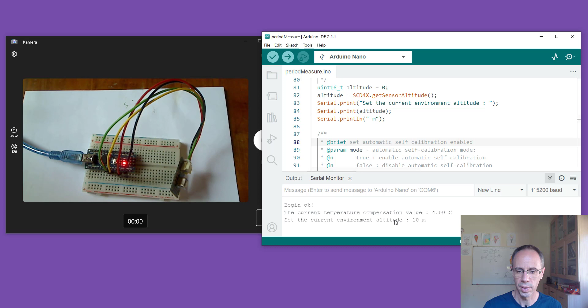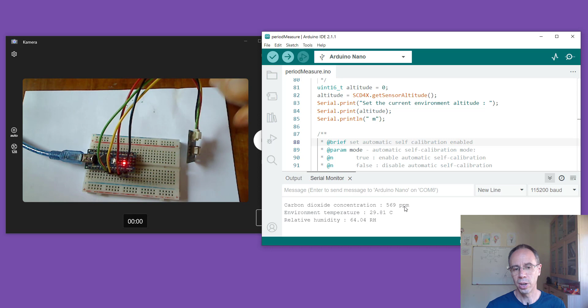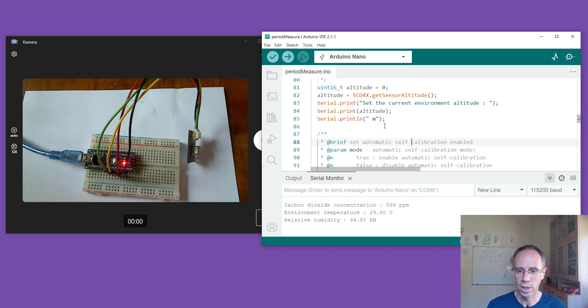You're seeing here it's going slowly down with these sensors. According to the datasheet, you have to put it at least once a week in an environment where the ppm level is around 400 ppm - meaning outside, or you have to ventilate well enough to get an exchange with outside air. But you can also do the calibration mode with a reference value if you have one.